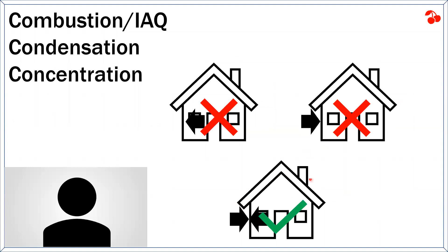But you ever seen this one? The homeowner has this really big house and they don't want to put one big 5-ton system in, which is good, that's a bad idea. So what are we going to do? We're going to bring in three 2-ton systems instead. And we're going to bring in all of our outside air onto one of these poor little systems. So I've got 5 tons of outside air going onto a 2-ton unit.